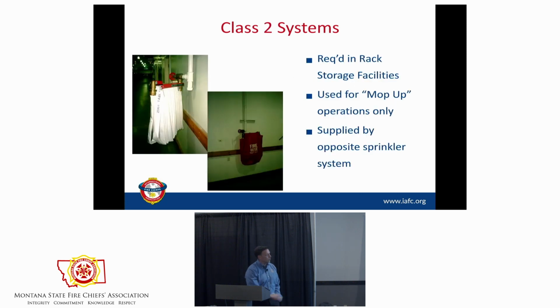But most of us are going to see what you see there. Now, these hoses, both in maybe a school or a theater, or our big box, actually are required. Our storage occupancies are required to have these. Many of us say, hey, don't use the hose. But it's a great option for us for what is called mop-up. It is not intended for active firefighting. So you have a storage facility that stores plastic on pallets on racks, 24 feet in height, 30-foot ceiling. Very common configuration. Smoke is lazy smoke, cold smoke. You walk in, you can hear the sprinklers operating. And there are flames running up, and you go, that's a lot of fire still.